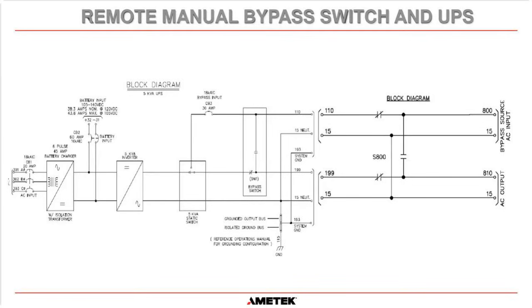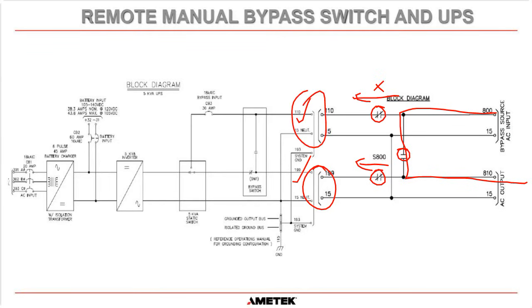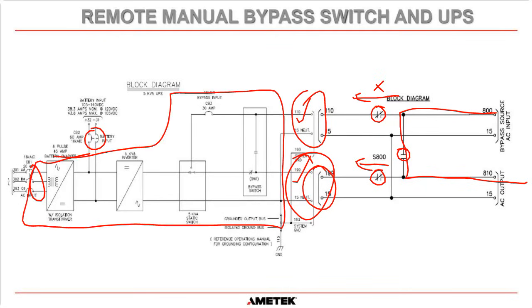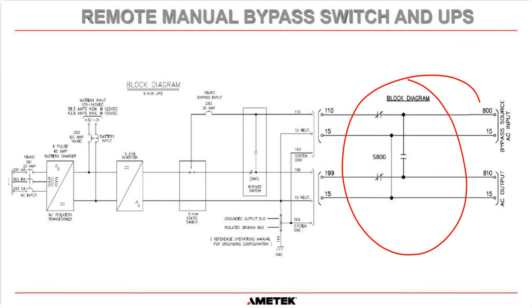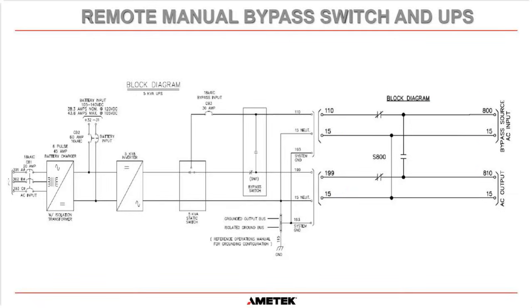But if you connect an RMBS to your system, when you go to bypass position on the RMBS, the power flows through here and out here. Then this contact here opens when we're in bypass isolated position, so power does not flow through there. So we are volt free here. And also this is open, so power can't flow through that way there. So these are volt free. If we isolate here and here, now the whole system is volt free and we can perform work in there without any issues whatsoever, and do it safely without any arc flash requirements and following NFPA practices. So an RMBS is very convenient when it comes to doing maintenance and if you wanted to replace the UPS.